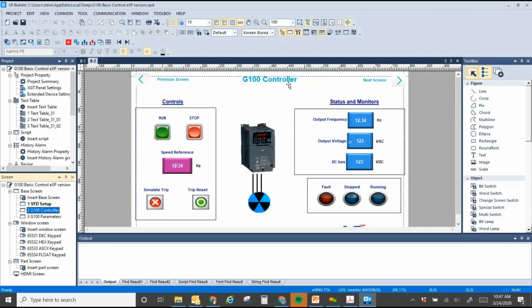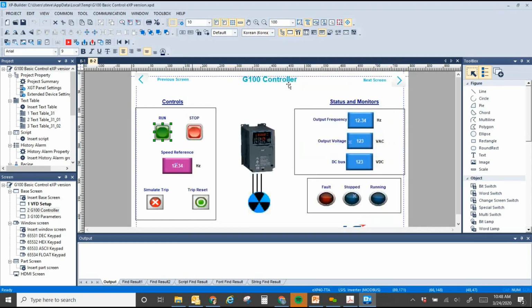For example, let's double click this button here. We can see that we're writing this to address 1 on our Modbus network, sending it to hexadecimal address number 6. Number 6 is your start command, or control mode. We're sending a value of 2, because 2 means forward run. If we want to stop it, we send a 3, which is stop.